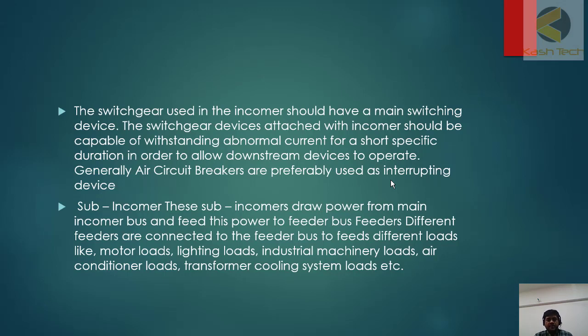The switchgear devices attached with incomer should be capable of withstanding abnormal current for a short specific duration in order to allow downstream devices to operate. Generally, air circuit breakers are preferably used as interrupting device.